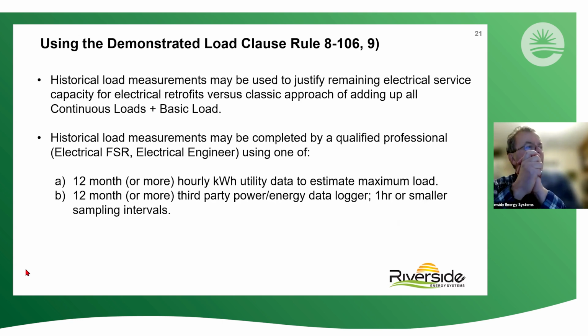So one of the most exciting bits of leverage we have available is the demonstrated load clause, which is Rule 8-106-9, where we are allowed by code to use historical load measurements to justify what our remaining capacity is, rather than using these worst case rules of thumb by adding up basic load and continuous load and assuming everything is concurrent. Those historical load measurements can be completed by a qualified professional. Typically, this would be an electrical contractor, an FSR, also known as master electrician, or an electrical engineer. And to do this, we would use either 12-month or more hourly kilowatt-hour utility data, which is available directly for download from BC Hydro.